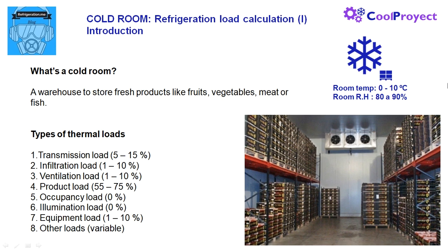In numbers five and six is the occupancy and illumination. We can ignore both of them for cold rooms because there are not usually people permanently working there. Number seven, we have to consider the equipment load — the heat due to evaporator fans and the frost resistances.